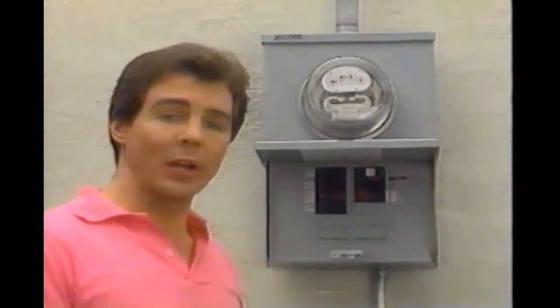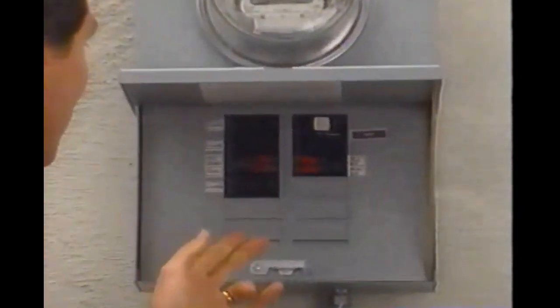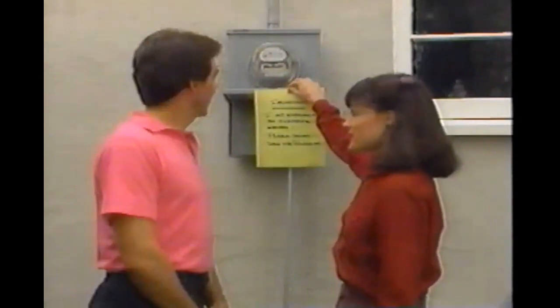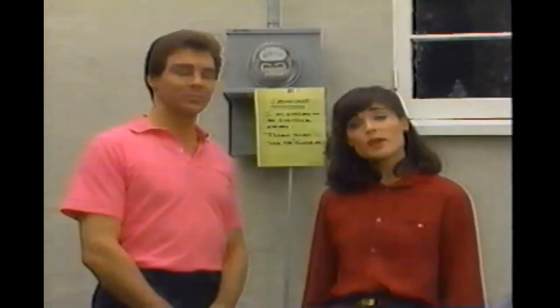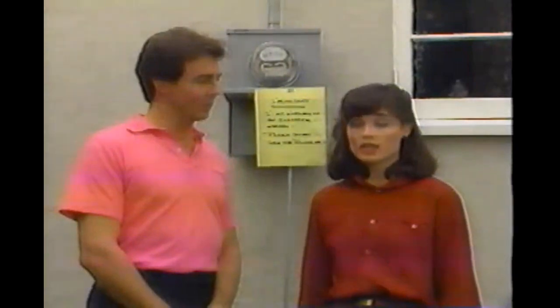Other homes have a circuit breaker panel like this that controls the power. This is the main switch. Anytime you work on the power in the house, this switch must be turned off. Turning off individual circuit breakers is not always safe, as sometimes more than one circuit feeds a box or a cable. It's also a good idea to tape a note to the service panel explaining why the power's turned off so that no one comes along and turns it back on while you're working on the wiring. If you follow our advice, you can safely make all the electrical repairs we're going to demonstrate.